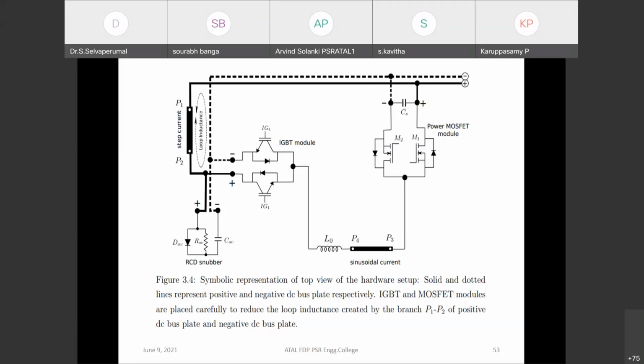So the layout of DC bus plates along with the connection of semiconductor devices is symbolically sketched in the slide. The layout of device ensures that additional stray inductance due to the branch P1 to P2 appears only across the IGBT terminal and not across the MOSFET terminal.